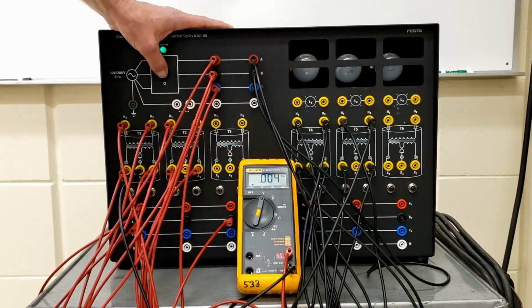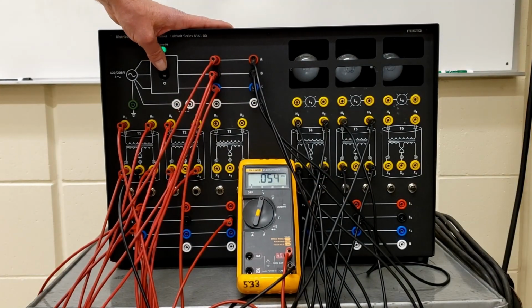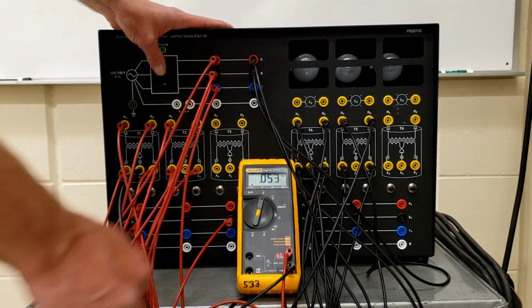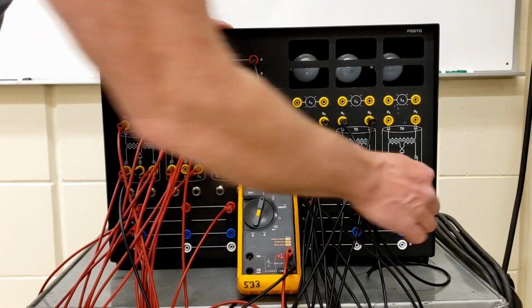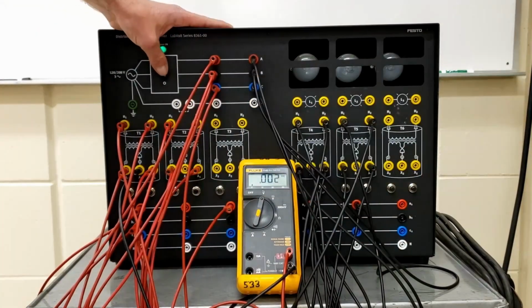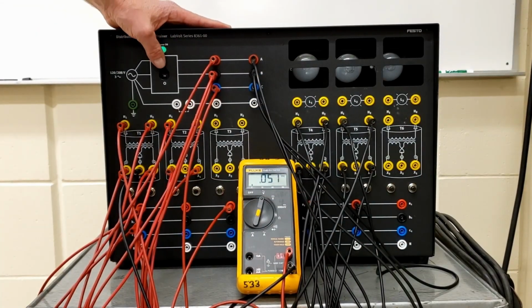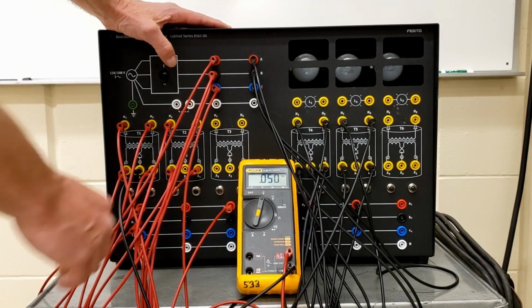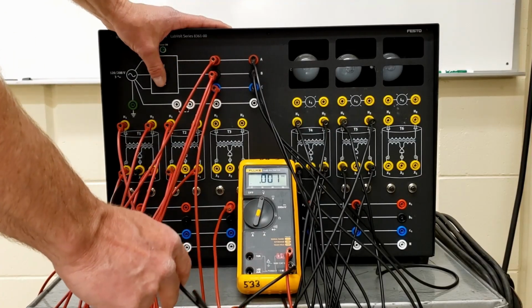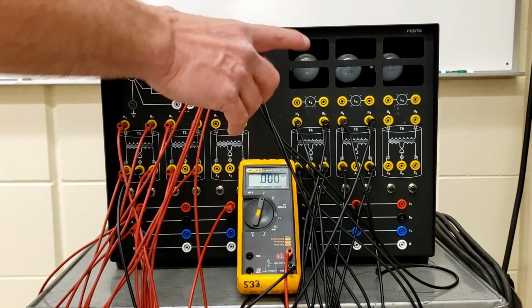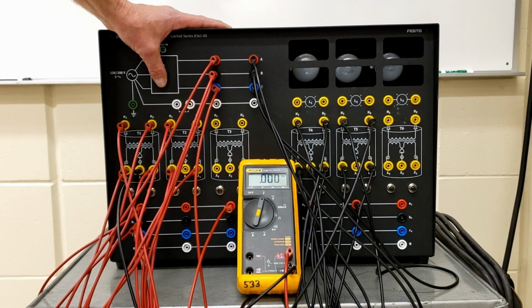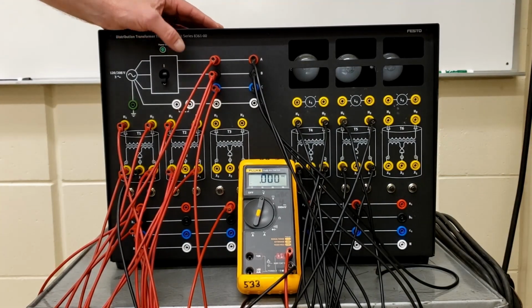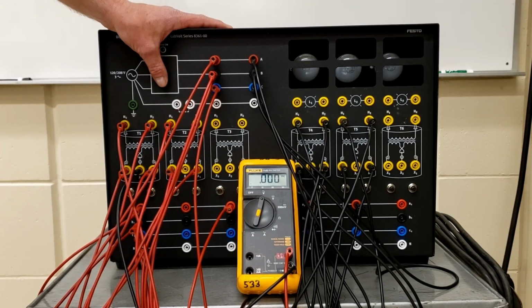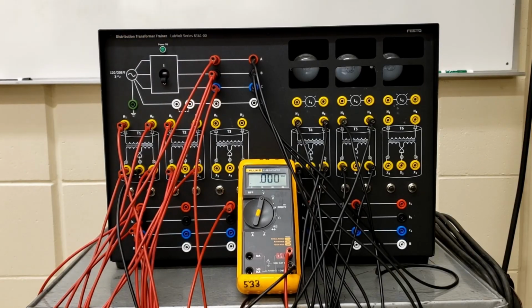Okay. Then next one, 0.053 volts AC, so no difference there. And on the A, no difference between those guys as well. Okay, so in order to see that zero voltage difference between the A, B, and C phases, it's crucial to have the X2 bonded to ground. Okay, now let's do the 180 degree phase shift on the second bank of transformers there.